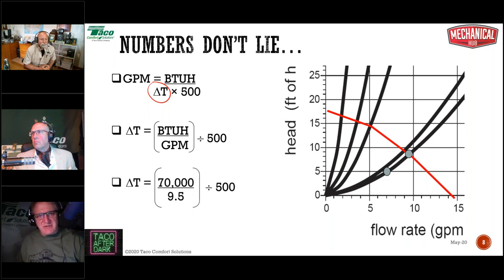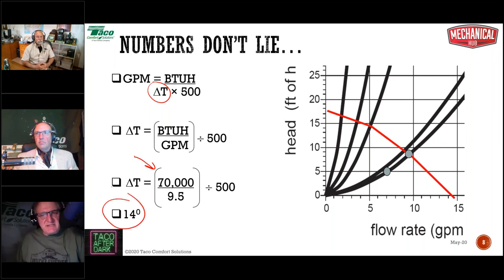So in this case, 70,000 BTUs under design condition divided by the 9.5 gallons per minute I'm using to deliver those BTUs divided by 500 gives me a delta T in this case of 14 degrees. That's the best delta T we're ever going to see in this system, boys and girls, on the quote unquote coldest day of the year, as provided there's no fudge factor built into any of this stuff.